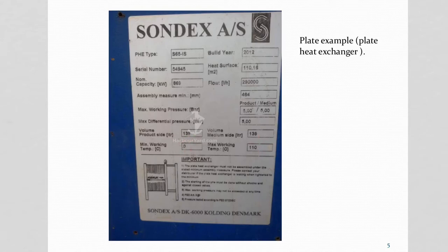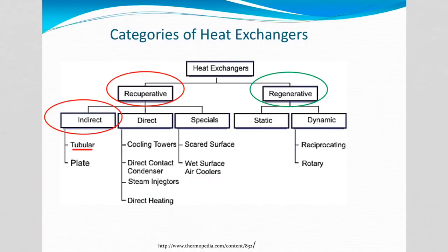They also indicate what the max working temperature is. Here 0 degrees, freezing point. Here is 110 degrees. It's the max that it can accept. Again, also related to the nature of the gaskets, which are nitrile, butyl, etc. They all have a temperature limit depending on their nature.